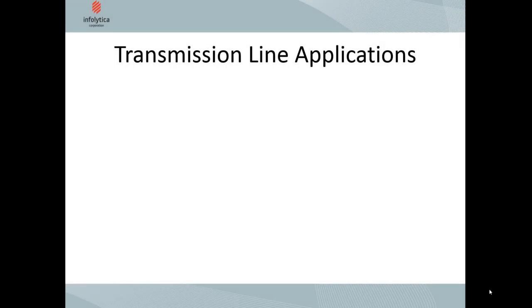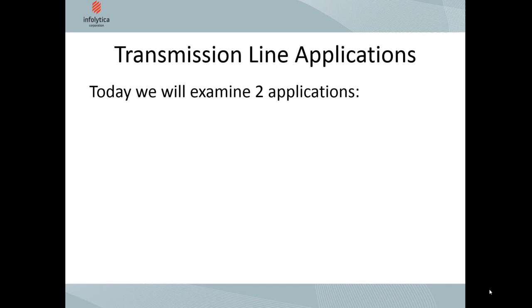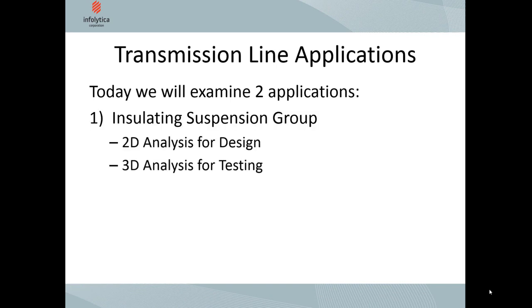For today's webinar, we will use ElecNet to analyze two applications. The first is a generic insulation string for transmission line suspension systems. The insulation string design is taken from an EPRI report which defines this generic design. We will examine the insulator using two types of analysis: first in 2D to look at designing the insulator, and second in 3D with the insulation string installed on a transmission line, where we will look at how the electric field stresses are affected by surrounding structures to validate the design.